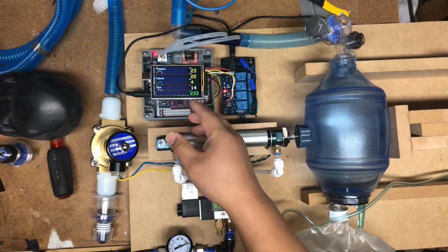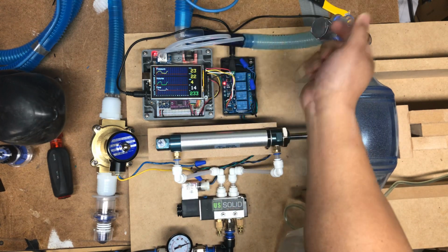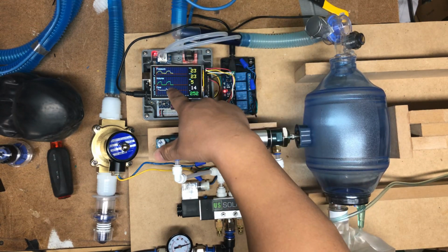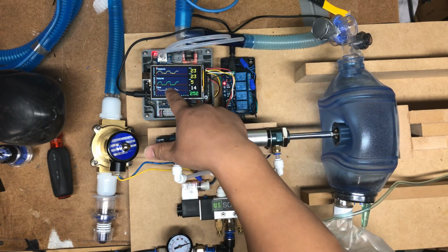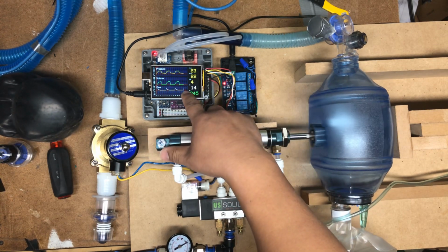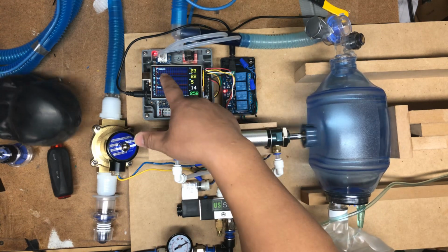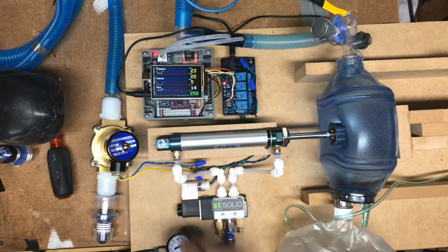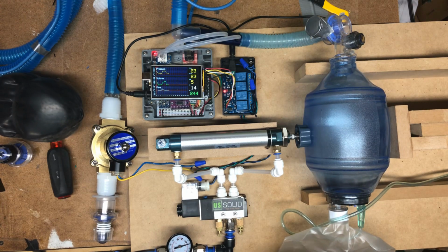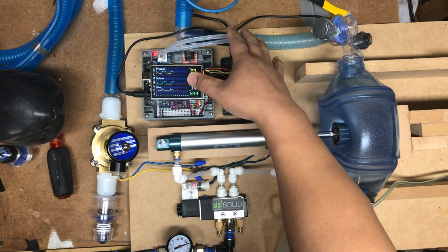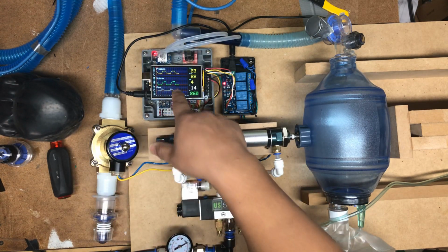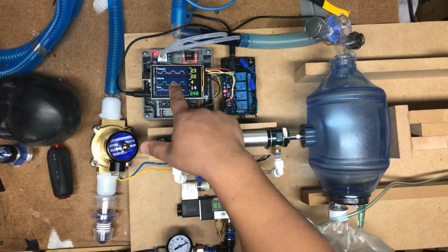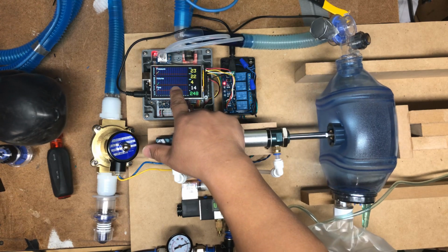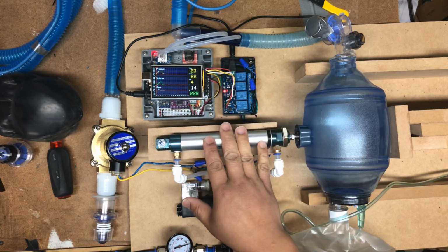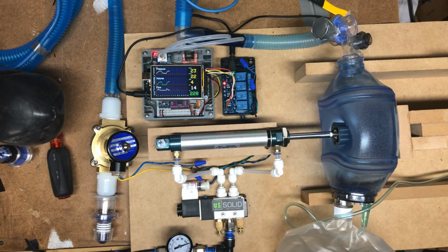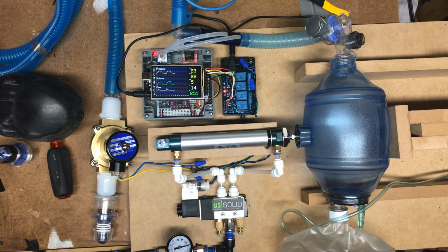Also note on the waveform that we only have a flow sensor on the inspiratory valve, so we don't have the negative flow from exhalation. We also don't have a realistic falling volume waveform, so we just assume that the volume drops to 0 before the next inspiratory phase. So we're going to add another flow sensor on the expiratory valve. That way we can monitor both the inhalation and expiration for the volume and make sure we're not having breath stacking. And that's our design.